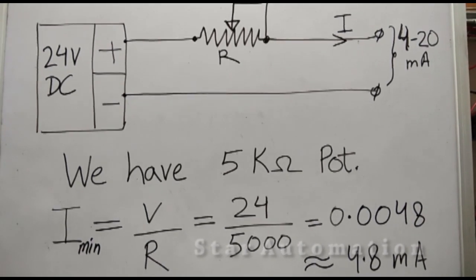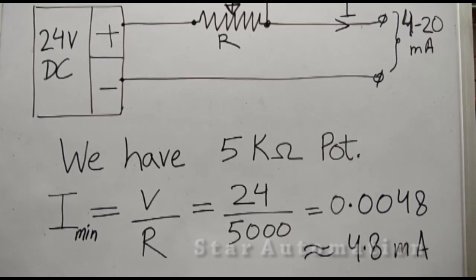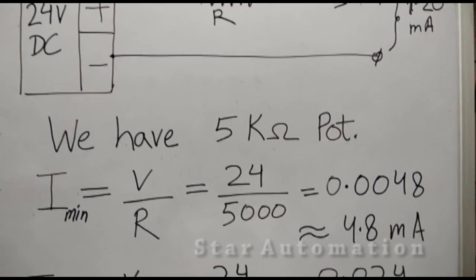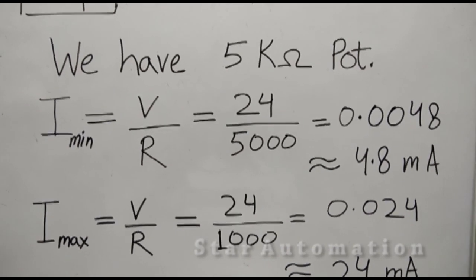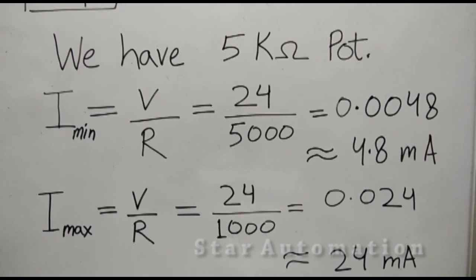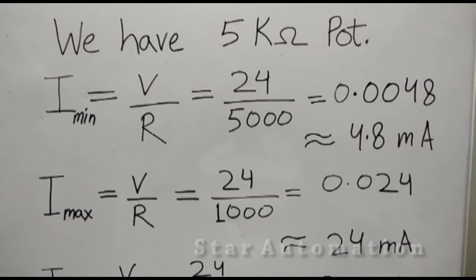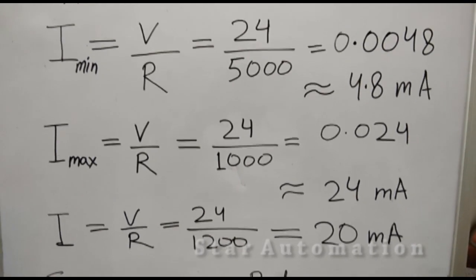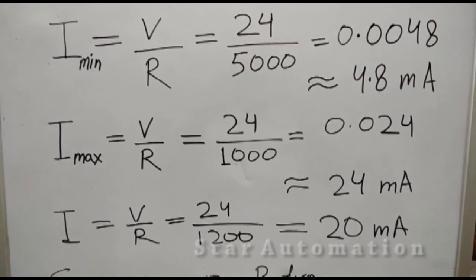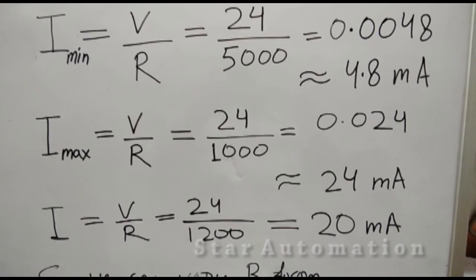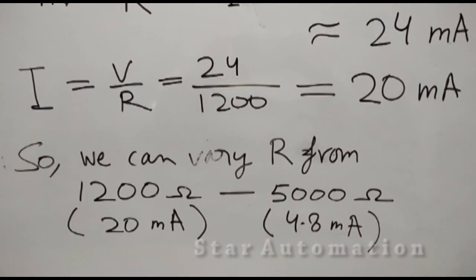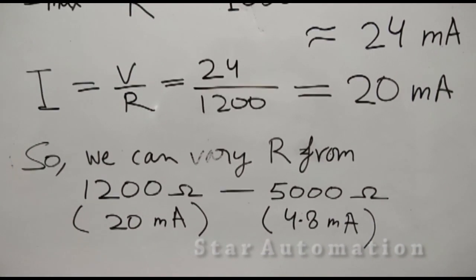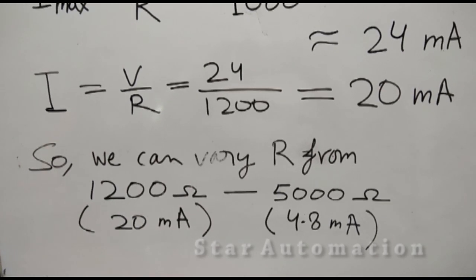Let us do some calculations. We have Ohm's law: V is equal to IR, so I is V divided by R. I minimum is 24 volts divided by 5000 ohm, which gives 0.0048, that is 4.8 mA. Similarly, I max is 24 divided by 1000, that is 24 mA. So R should be 1200 ohm to get 20 mA, and we can vary R from 1200 ohm to 5K.